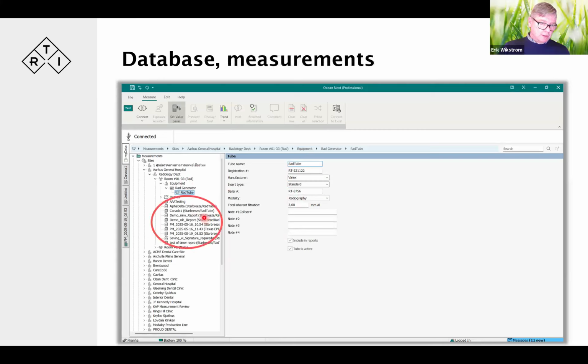Once we're in there, the measurements that we do in this room will be saved under that room together with the equipment. So these are all measurements performed in this room, and whether or not it's with this specific tube depends on if it's active. It'll pick the active tube when we're doing that. So when you replace a tube, you unclick this one and make a new tube entry with the serial number, and you'll trace the performance based on that tube from that point onwards.